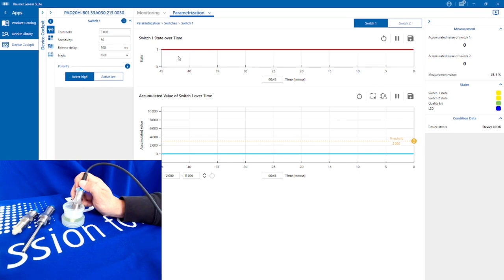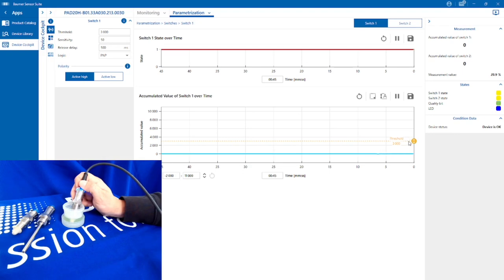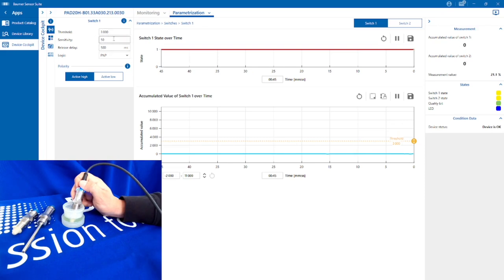As soon as I start to see any air, both of these two switch states will return to zero as soon as we cross these two threshold lines: switch one at 3000 and switch two at 7000. On the left hand side you can see the threshold I've set there, and also the sensitivity that I've set. 100 is the most sensitive to air, 50 is halfway between, and zero is the least sensitive.